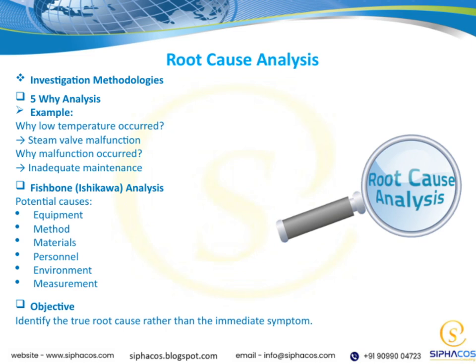That's where root cause analysis comes in. One common tool is the 5 why analysis, where we keep asking why until we uncover the underlying issue. For example, a low temperature might be traced back to a steam valve malfunction, which itself was caused by inadequate maintenance. Another method is the fishbone, or Ishikawa analysis, which helps us explore all possible causes, from equipment and methods to materials, personnel, environment, and measurement. The goal? To find the true root cause, not just the surface symptom.